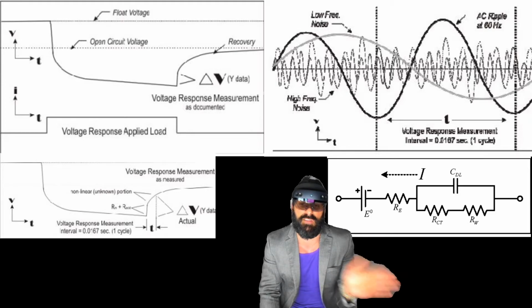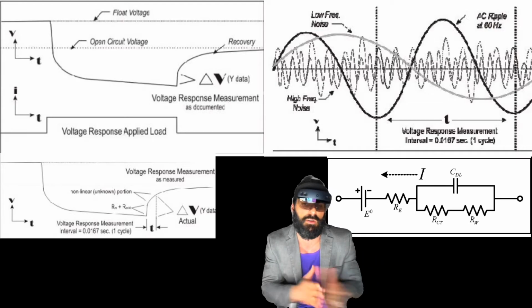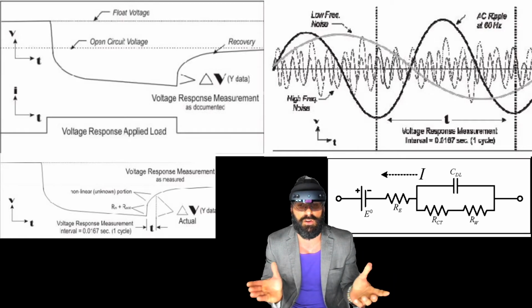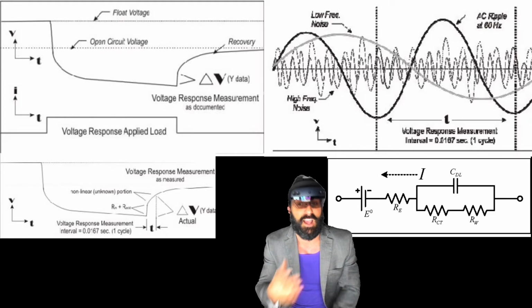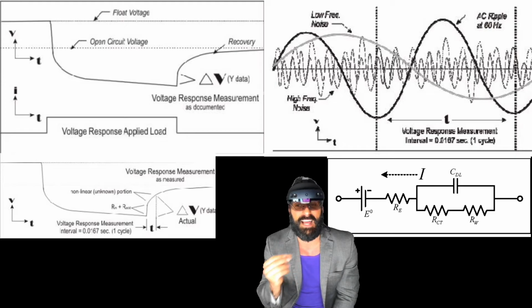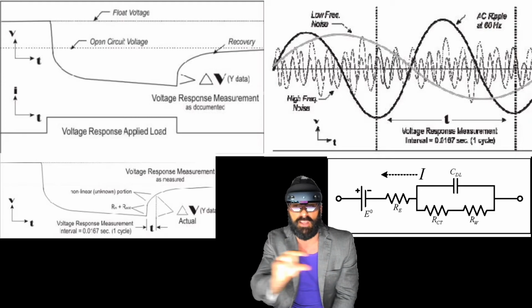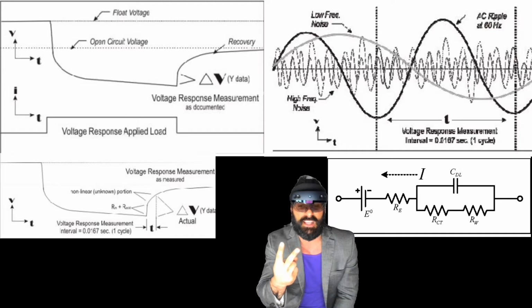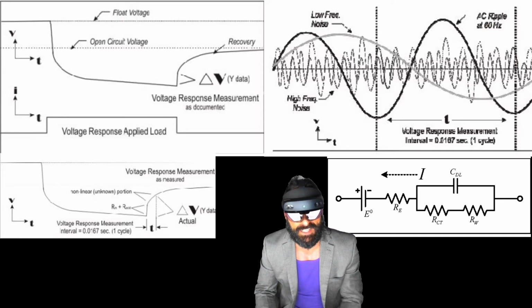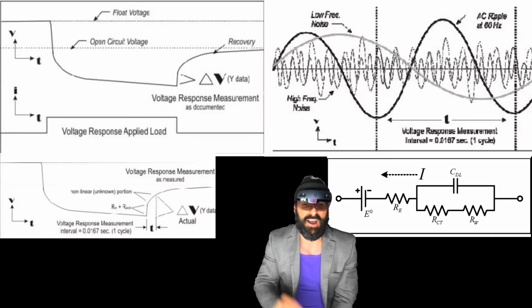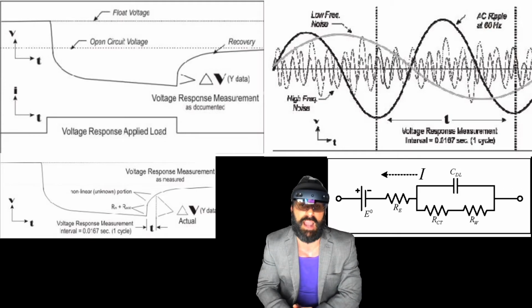So what they're doing instead of DC is injecting an AC signal into the battery across the anode and cathode. That frequency can vary from 50 hertz to 1,000 hertz, whatever they choose depending on the capacitive reactance. I've always hoped that they have an intelligent system there that can see that there's noise riding on the DC floor, and they can switch the frequency to 500 hertz to mitigate this. I haven't seen a system that does this yet, but we'll see in the future. But at specific frequencies, the inductive and capacitive reactance can converge and it will result in a minimal voltage lag.